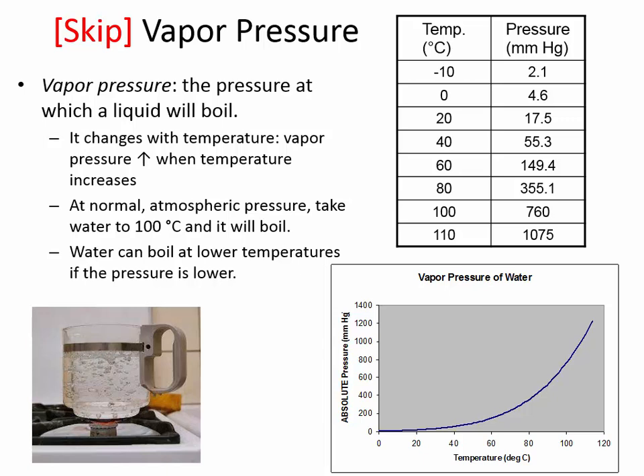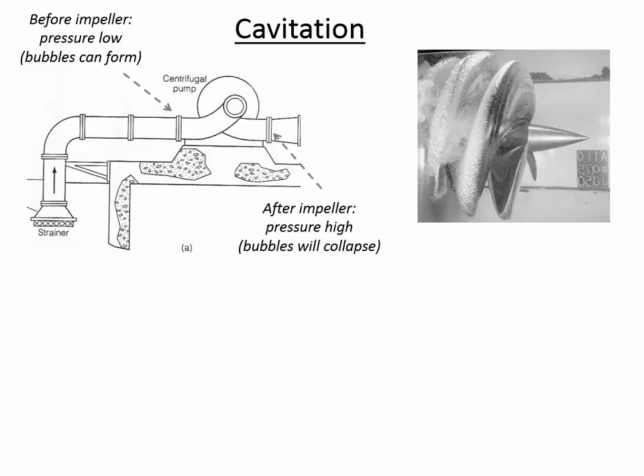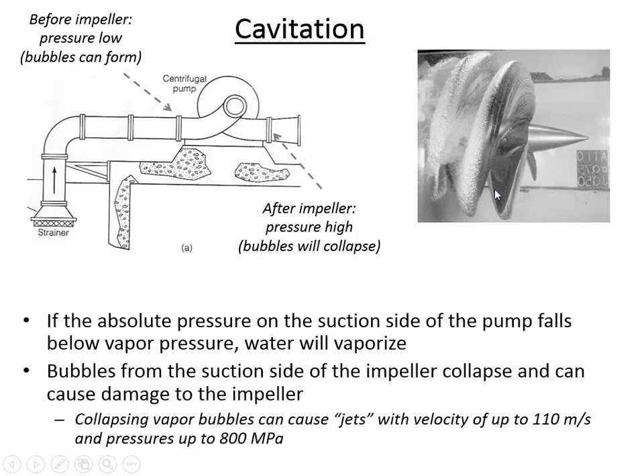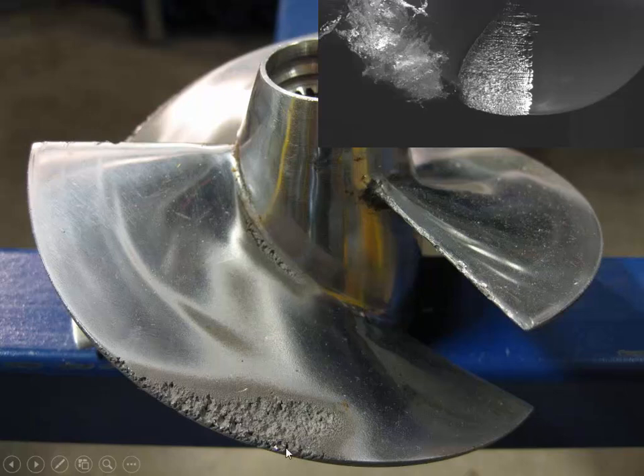You can either have a low pressure by pumping out air, or you can have a low pressure in a system in this case just because energy is being lost due to pipe friction as you keep going along this. All of a sudden you may get to the critical point, and it may not be in the pipe itself. It might just be right along the face of the blade that you've got that really low pressure. It might just be at one tiny little spot that the cavitation occurs, but that's enough. Any other questions?